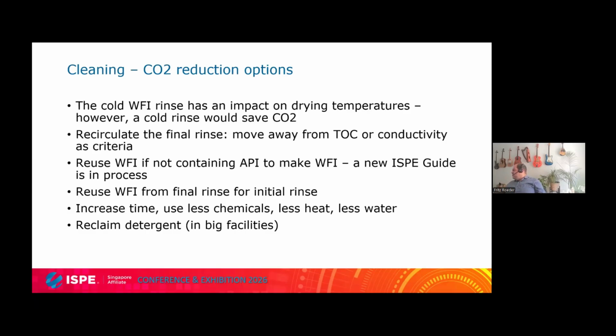Next one: how do you determine how many times we can reuse WFI? You have your quality parameters that you measure during purification - if you reuse it before RO again, or bring it into the cleaning cycle, then you're going to rinse that cleaning water afterwards anyway, so it's a one-time cycle, let's say.